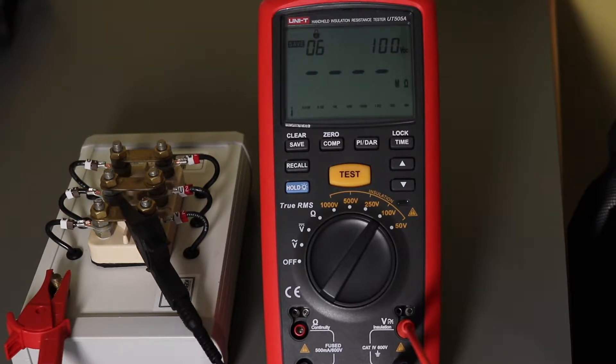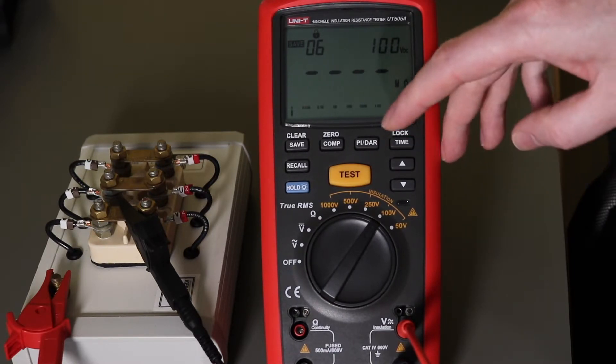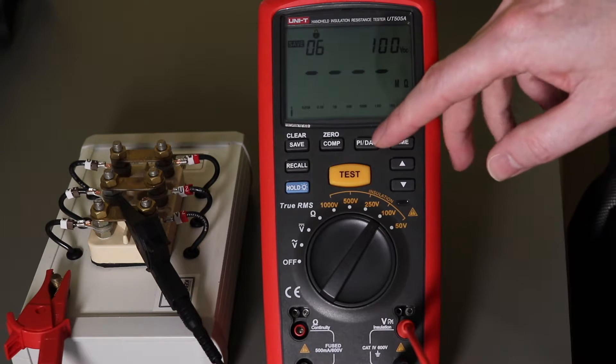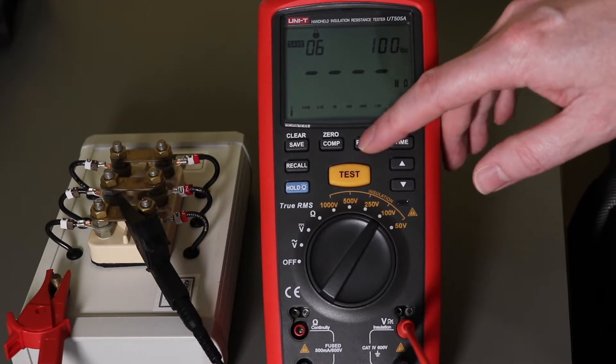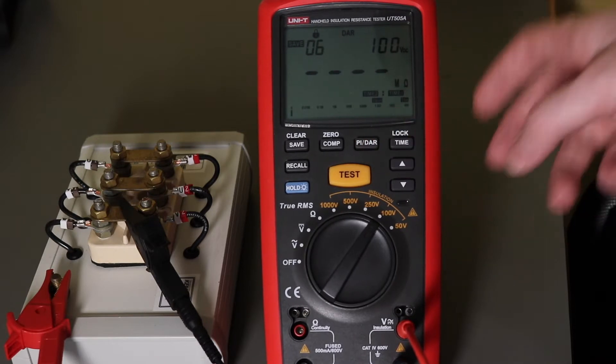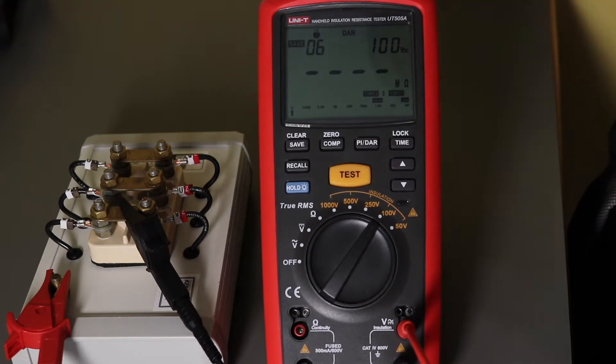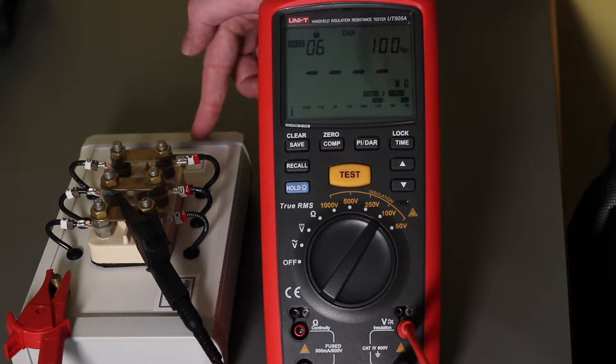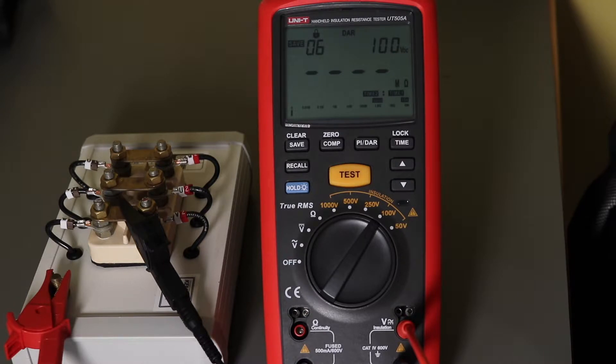Following on from the problems I had when demonstrating this unit - the unit not stopping when it was on PI/DAR test. I've not observed that before, so what I'm going to do is set this up for another DAR test. I've got it on a little winding simulator back here, so it should produce a proper DAR value this time and we'll see if the test does cut out.